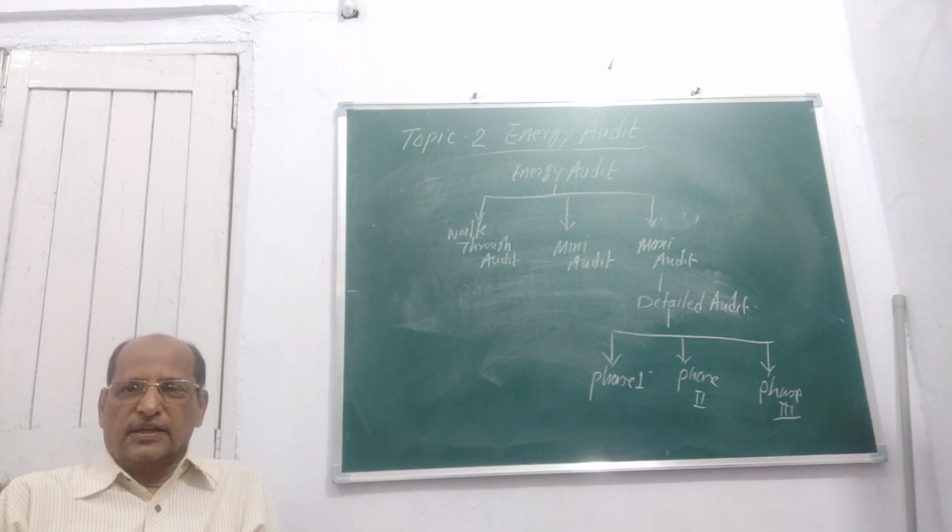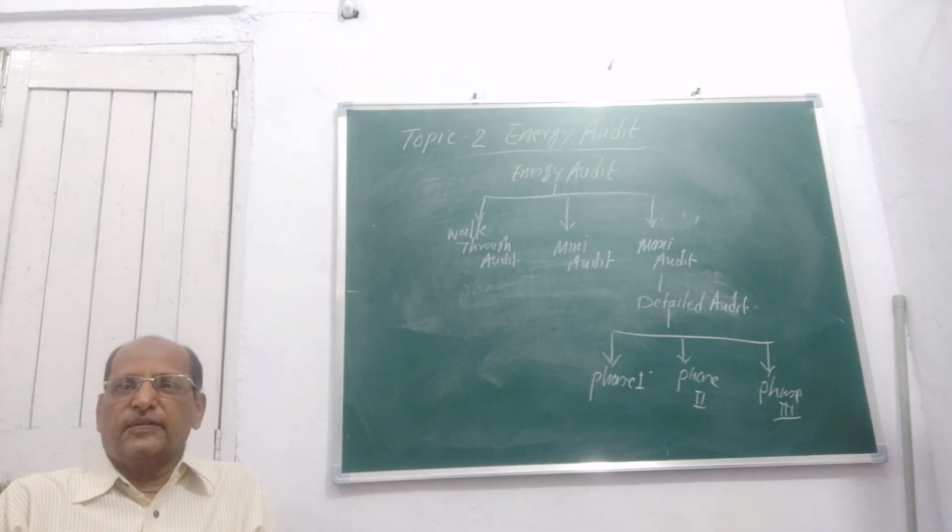So you convert HP into kilowatt, and if it runs for 6 hours, then you multiply this kilowatt by 6 hours and apply the efficiency as per the standard given. Normally motors or drives are designed for a maximum of 85% efficiency. So according to 85% efficiency, what is the consumption for 6 hours?